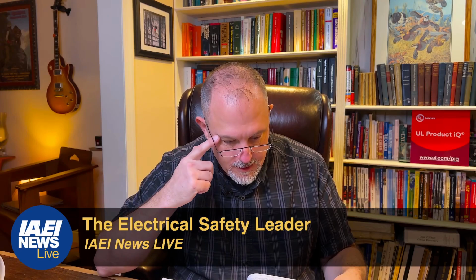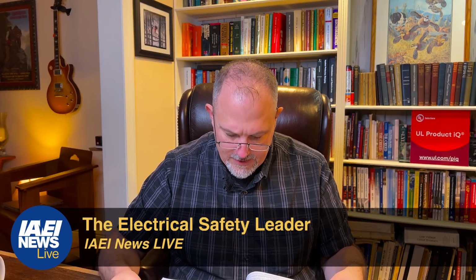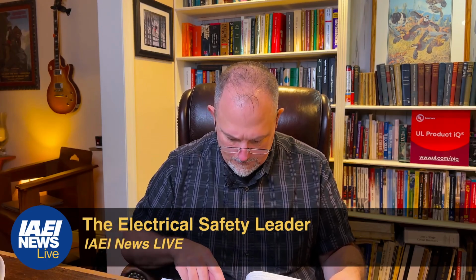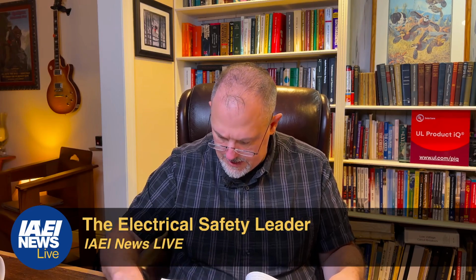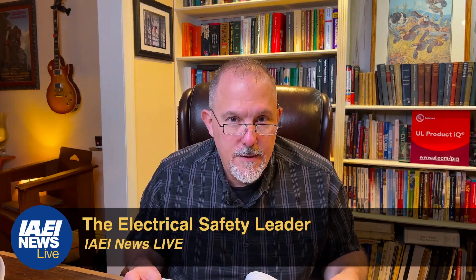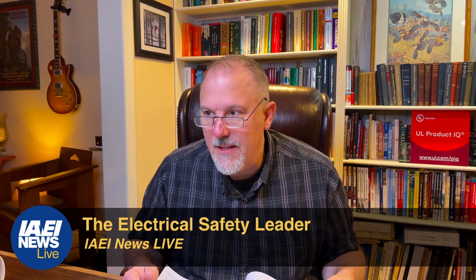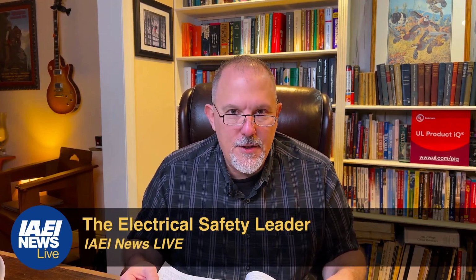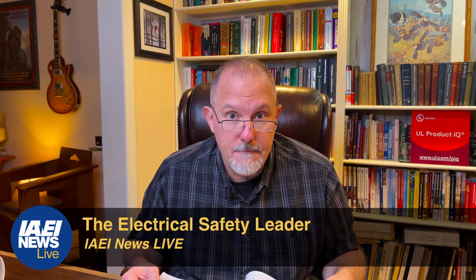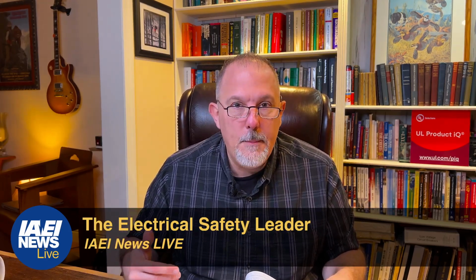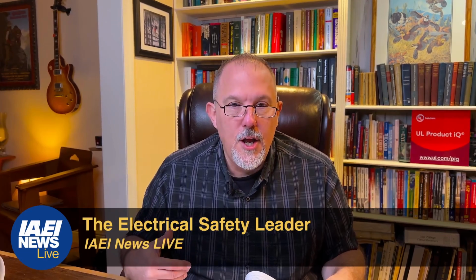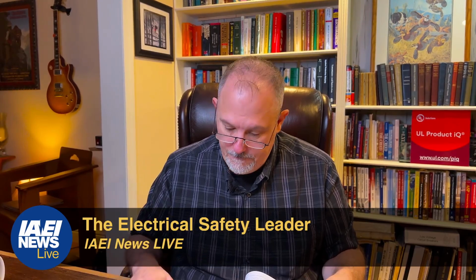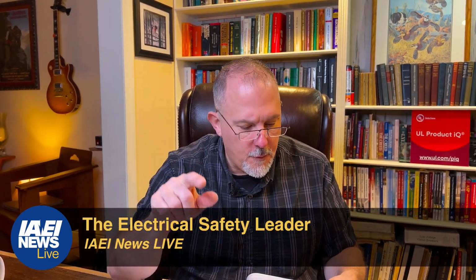All right. So general installation requirements: 404.7 indicating, 404.8 accessibility and grouping, general use snap switches 404.9, and 404.10 mounting of general use snap switches, dimmers, and control switches. So this is mounting. Now, if I'm dealing with a wireless controller, how am I supposed to mount this thing? It's not covered in 404.10, because if it's a wireless controller, 404 doesn't apply. Bada bing, bada boom. 404.11, circuit breakers as switches.